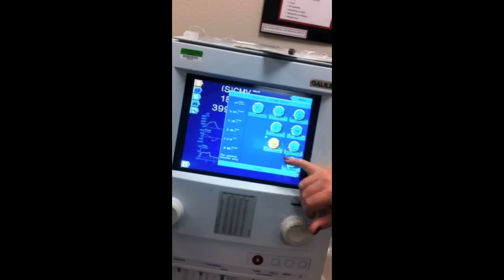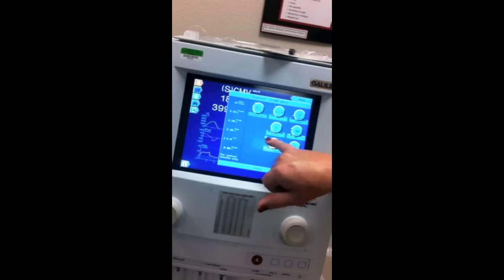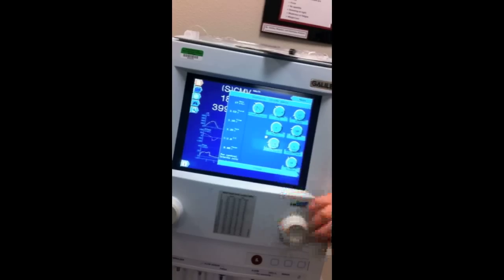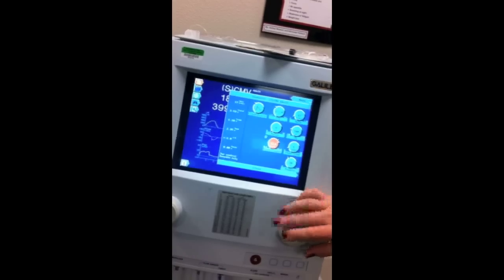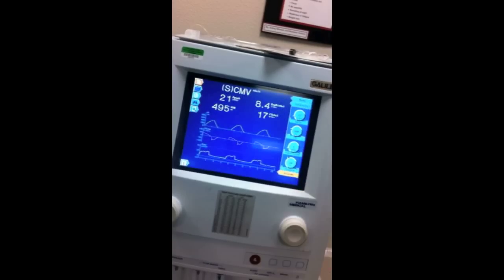It's negative. It's at -2. Flow trigger is at positive or negative numbers? Positive. So if you want to change this one, see this little dot right here? You put the orange at the dot. Watch what happens. Trigger off, flow trigger. And then we can go down to it and set it. So we'll just put it at 3 for now. Typically, though, the vents will auto-cycle if we don't have this way up. So for now, I'm just going to put it up. And then we do close, and we'll just ventilate.